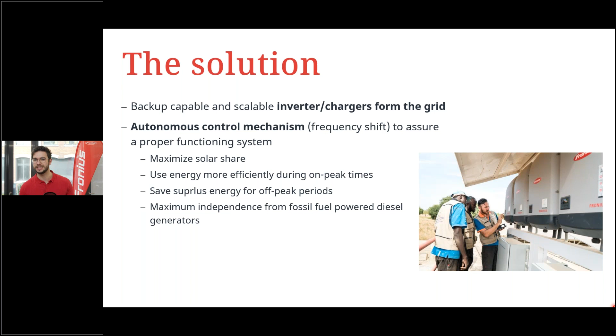Okay, and this is how it works now. You have a grid or not. So let's say there is a grid, then you have the inverter charger. And on the inverter charger, you connect the AC to the loads. And in between load and inverter charger, you then have the possibility to connect the Fronius inverter. Like every system you would do on a grid parallel solution, you just do an AC coupling. That's basically it. And then there are a few more options you can do.